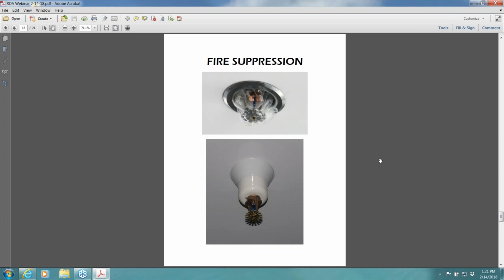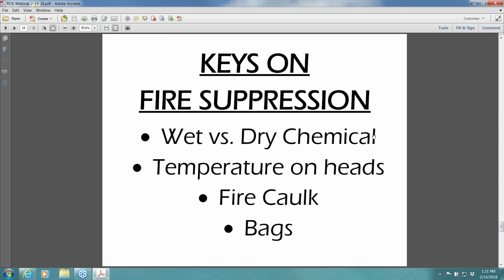So they will put in either a wet system or a dry system. That's the first key on fire suppression. If the customer's building is sprinkled, it'll be less expensive for them to extend that sprinkler system to the paint booth and drop a few heads in there to add fire suppression to the booth. What they have to look at is someone — either a mechanical engineer or the fire suppression specialist — will run a hydraulic calculation on the amount of water pressure available to the building. You may find that although the building is sprinkled, they don't have any other capacity to add additional heads.